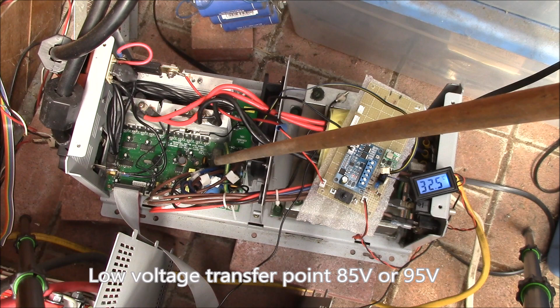This is what's called an H bridge, I'll talk about that in a bit. It runs that power through these two heavy cables into this transformer, producing an AC waveform that comes back on this smaller red and black wire through the relays and out to your critical load. Then if the grid power comes back on, the relays switch and go back into basically a bypass mode.